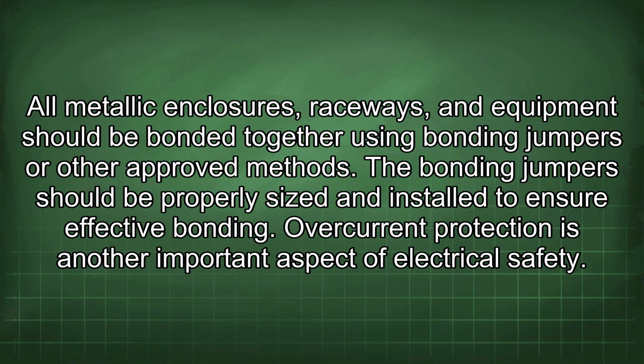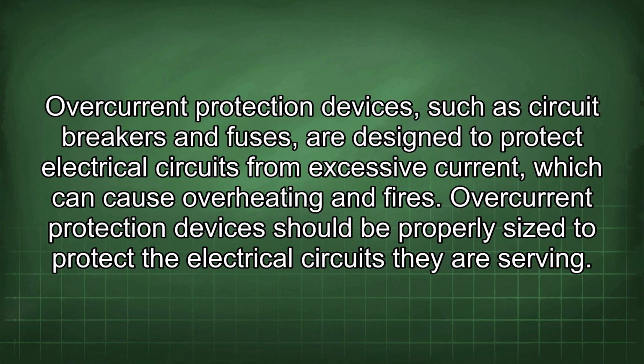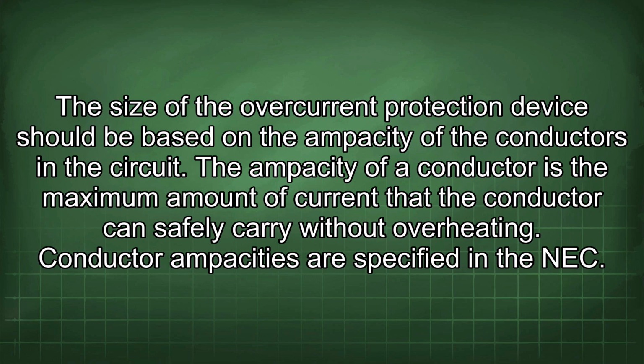Overcurrent protection is another important aspect of electrical safety. Overcurrent protection devices, such as circuit breakers and fuses, are designed to protect electrical circuits from excessive current, which can cause overheating and fires. Overcurrent protection devices should be properly sized to protect the electrical circuits they are serving. The size of the overcurrent protection device should be based on the ampacity of the conductors in the circuit. The ampacity of a conductor is the maximum amount of current that the conductor can safely carry without overheating. Conductor ampacities are specified in the NEC.